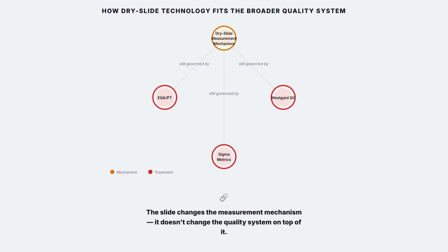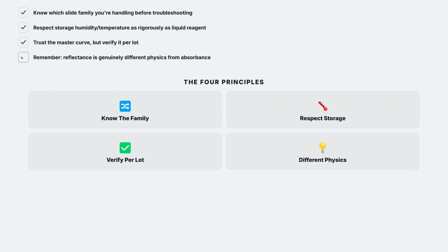Understand which slide family you're handling, colorimetric or potentiometric, before troubleshooting anything. Respect storage, humidity, and temperature as rigorously as any liquid reagent. Trust the master curve, but verify it per lot. And remember that reflectance photometry is genuinely different physics from the absorbance readings you're used to.